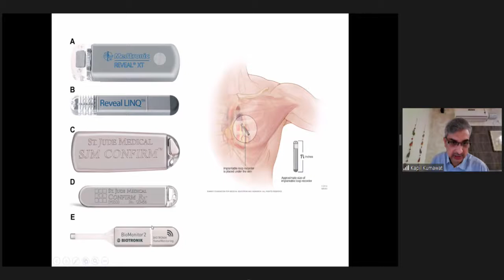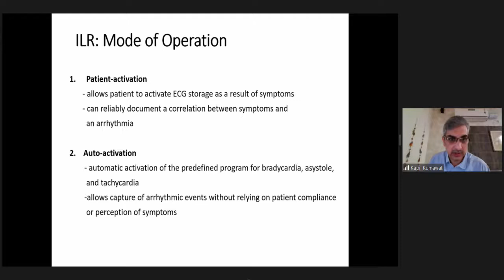Now, ILR acts in 2 modes. Patient activation: after the event, the patient can activate the device with a handheld gadget given to the patient, and it marks an area of interest, and the ECG before that event and after that event can be saved in the memory of the ILR. There is also auto activation. Whenever the device detects any bradycardia, asystole, or tachycardia, it automatically stores the relevant sections of ECG in its memory.